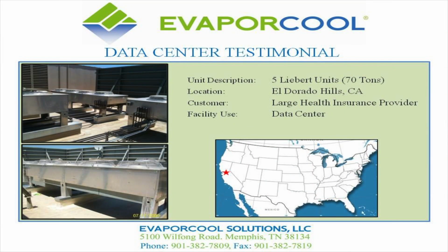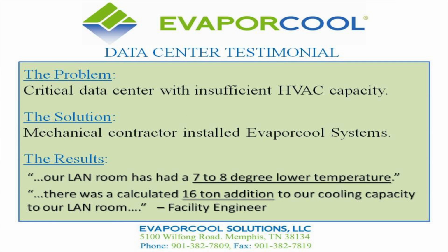This is another example of a data center project we did in El Dorado Hills, California. Their issue was capacity, not being able to put another unit on the roof. They brought us in for a solution, and our solution was to help them increase tonnage. Through putting on the system, we were able to calculate a 16% tonnage savings that they couldn't have found otherwise, since they didn't have room to put another unit on the roof. The solution did help them lower temperature and also increase tonnage capacity.